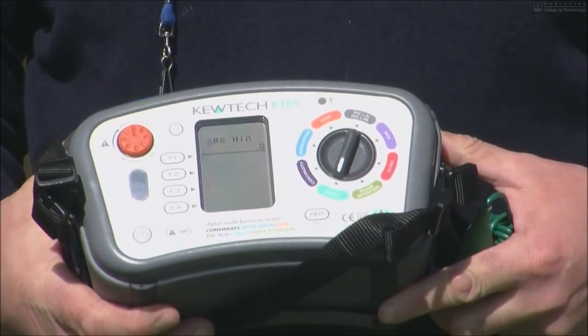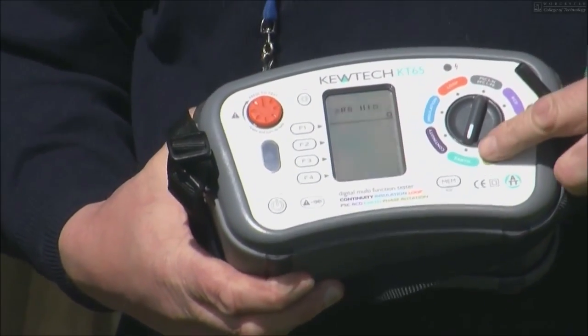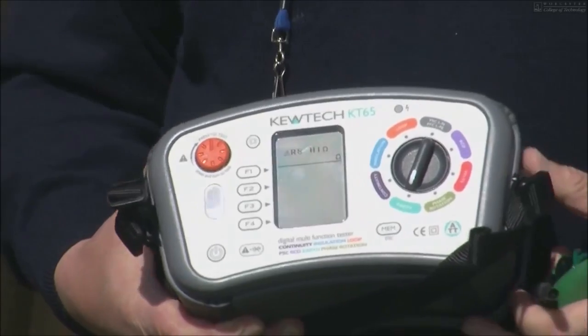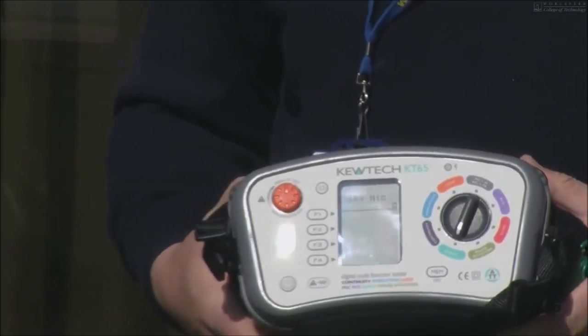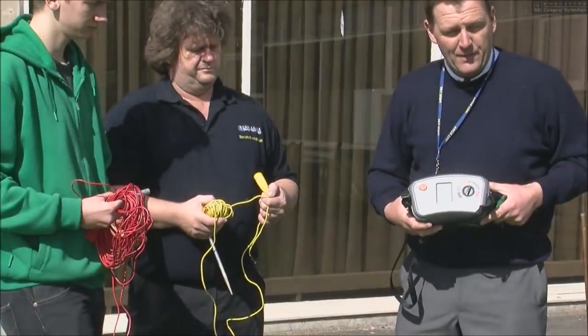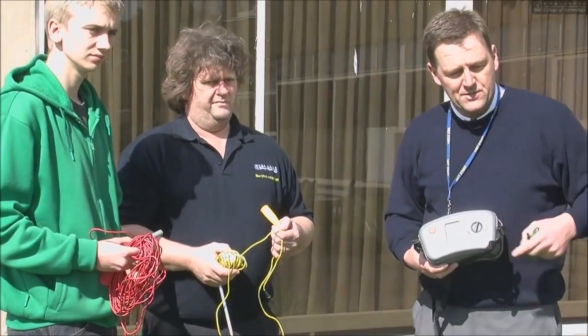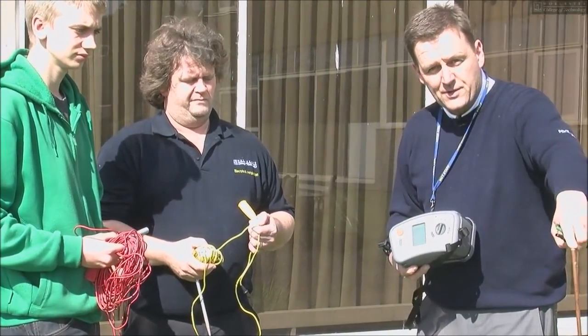This is the tester we'll be using. We've got it set onto the earth electrode test. My colleagues have a yellow and red lead, and I have a green lead. We're now going to stretch these out approximately 30 metres away from the earth electrode.